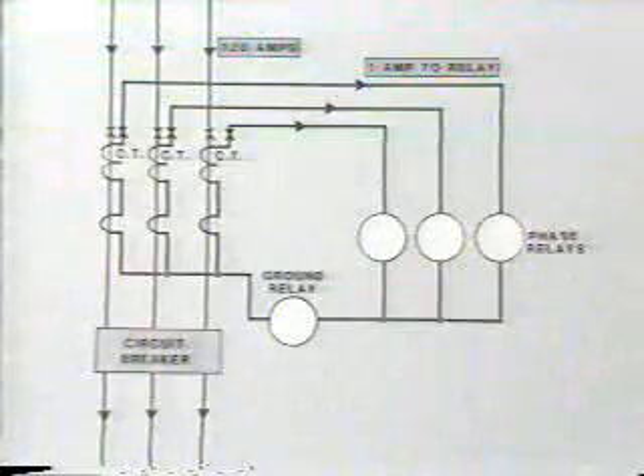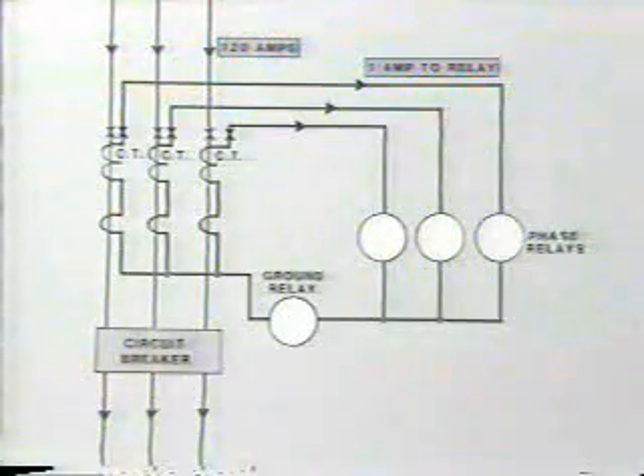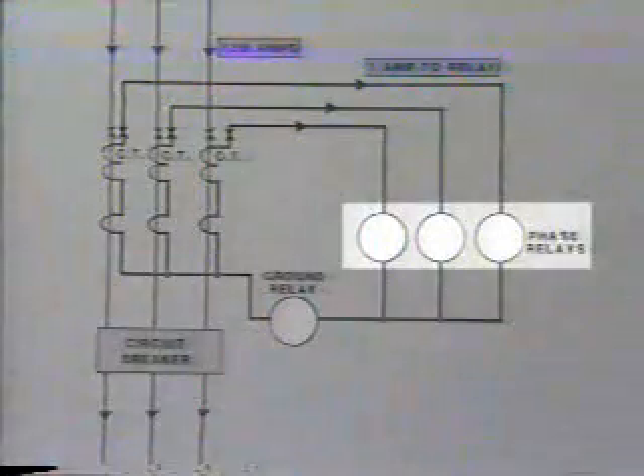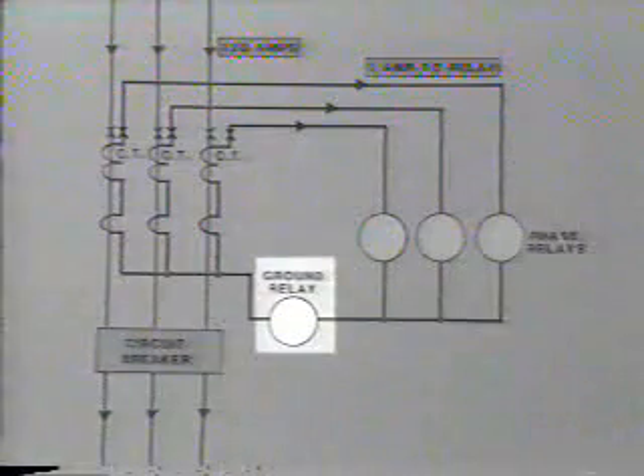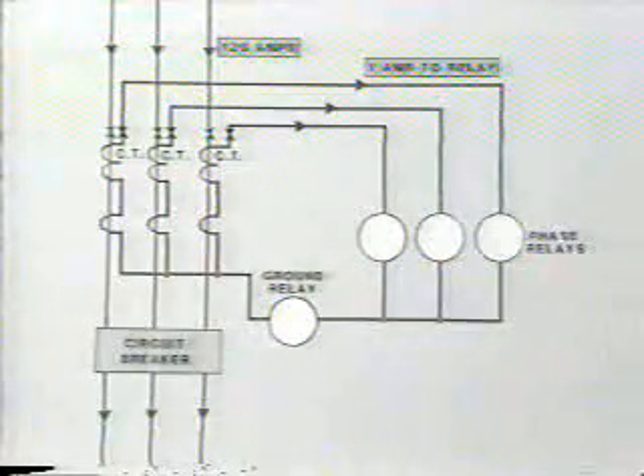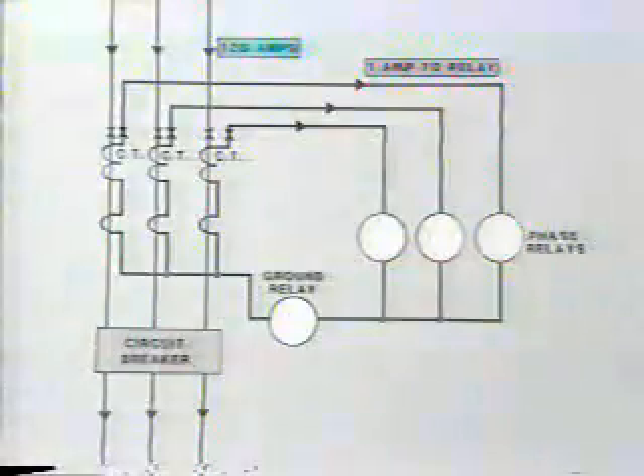Of course, the circuit that we have been studying is extremely simple, and we have not specified any particular type of relay. You know that this is going to get far more complicated as we go along. For example, considering the three phases of the same circuit, we now have to include three relays, one per phase, plus a ground relay, all with their separate CTs and sometimes VTs as well. But before we go on, let's take a short break. Please switch off the tape now and thoroughly review this material in your workbook.